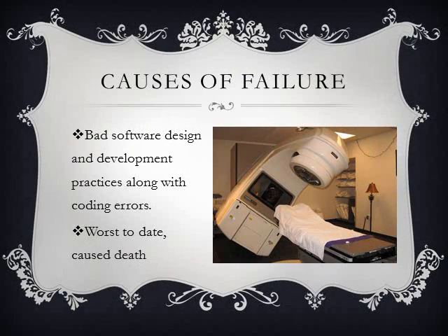found. The main causes of the failure were seen to be bad software design, which ended up causing death. Researchers who investigated the accident found several contributing causes. These included the following. The AECL did not have the software code independently reviewed. The AECL did not consider the design of the software during its assessment of how the machine might fail.